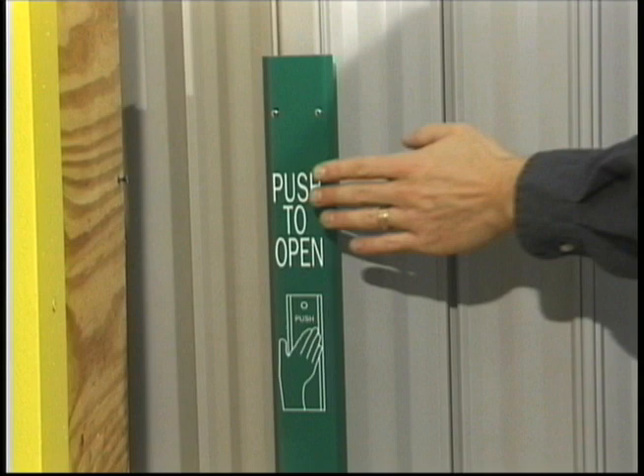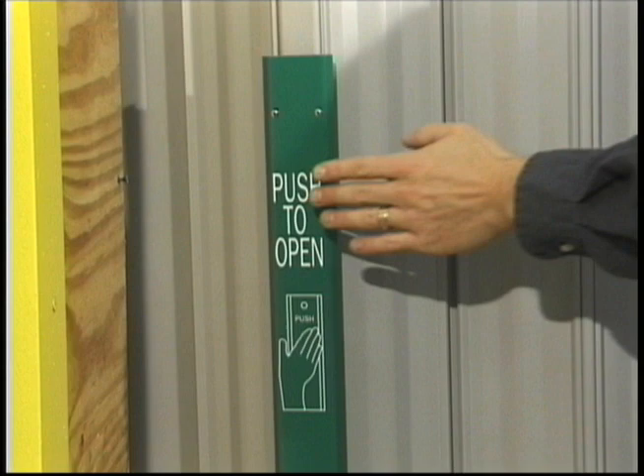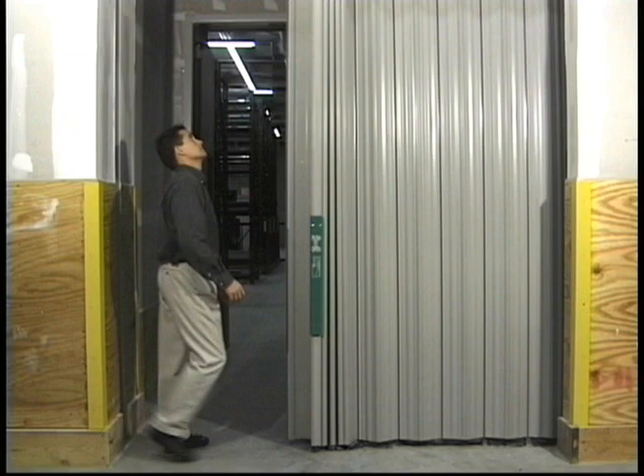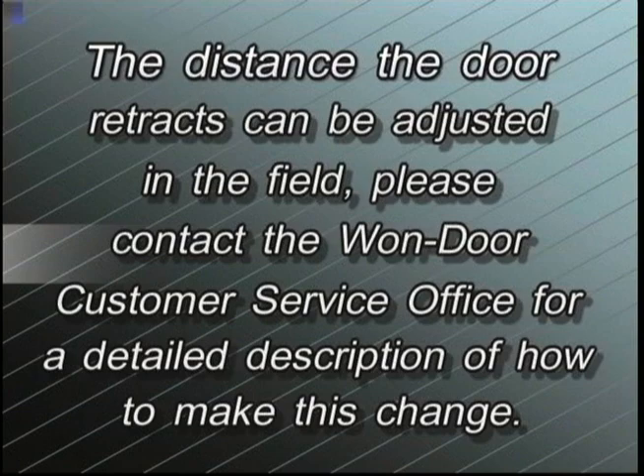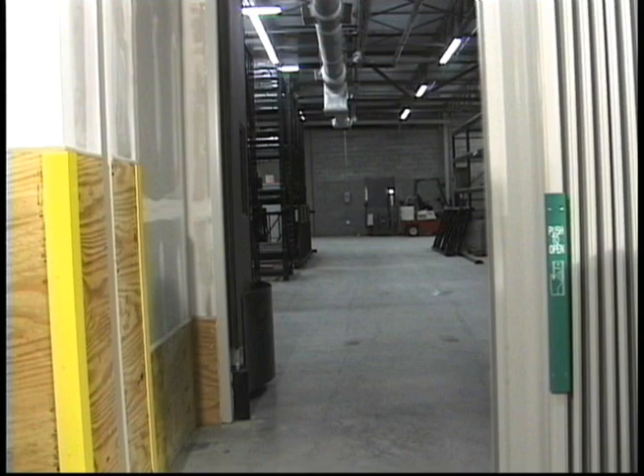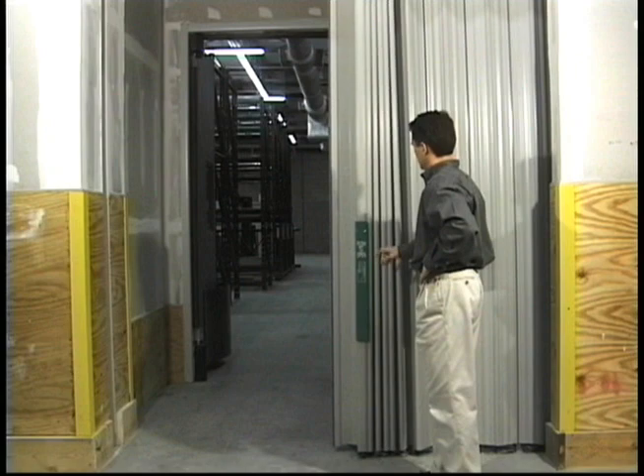The first and most common method is to apply pressure to the green push-to-open panel as shown. This device is used for egress in fire situations. Only four pounds of pressure applied to this panel will cause the door to retract from its closed position a preset distance. The distance the door retracts can be adjusted in the field. Please contact the Won-Door Customer Service Office for a detailed description of how to make this change. After retracting to the prescribed opening width, the door will pause and then recycle closed. If the exit hardware is activated again while the door is in the process of opening, it will simply open an additional distance equal to the established opening width.